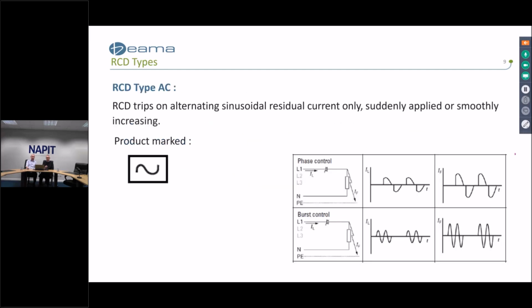So we're just going to go through the different types, and to take the types one at a time, we'll firstly briefly look at Type AC, and this is the product that will detect and open on an alternating sinusoidal residual current only. So whether it's sudden appearance or smoothly increasing, it will detect and trip on a sinusoidal current. But also you will see on the waveforms that we put on the screen, it's not just a pure sine wave. It is actually a sine wave where it's kind of switched or phase controlled or burst controlled, such as might be used on a dimmer circuit.